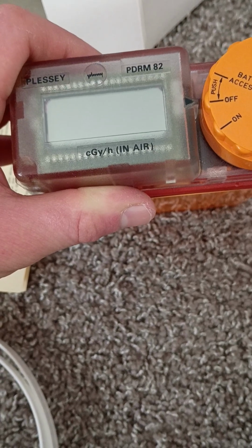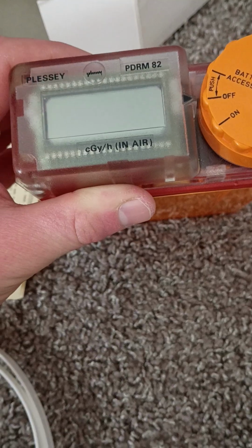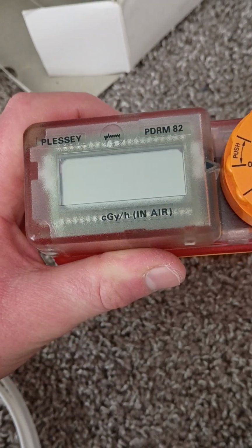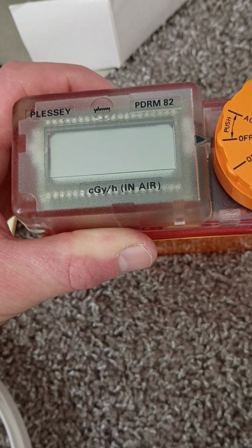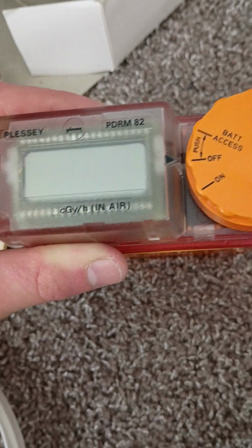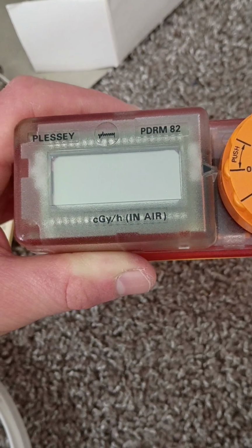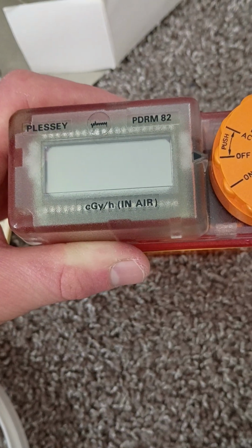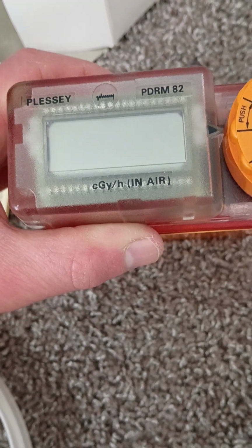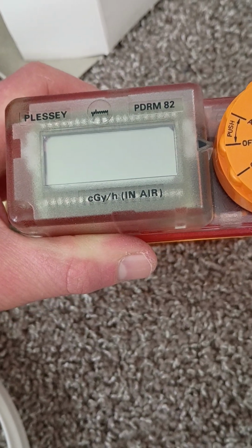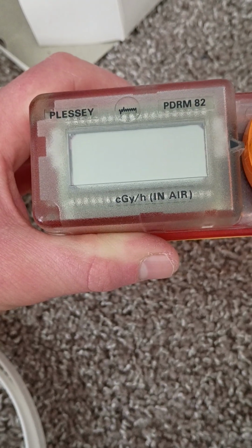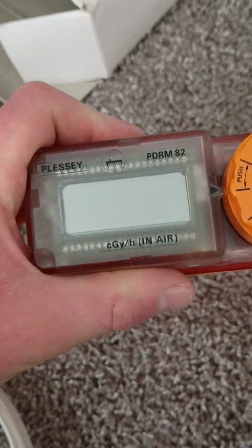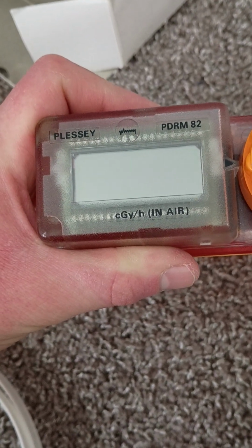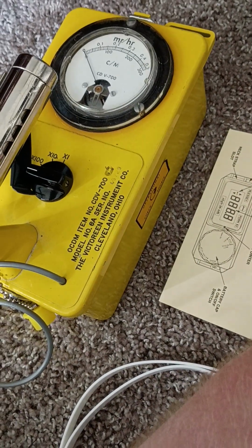Now, Cresson Kearny, the author, he continued to update that book into his retirement, and in an edition that came out in the 80s, he talked about this specifically as one of his recommended meters for folks to pick up. He did say that a friend had a unit and tested it with, I believe it was, a high-energy gamma calibration source, and did find that there were some problems with it, and the meter was sent back to Plessey and replaced. So some of these units could very well be slightly off, but then again, given the 40 years in storage and no calibration, I wouldn't trust it now anyway in a nuclear disaster, but still just a little interesting piece of history. Otherwise, this is fairly unknown in the United States. Again, it's mostly the CDV 700s and 715s that are discussed in the United States.